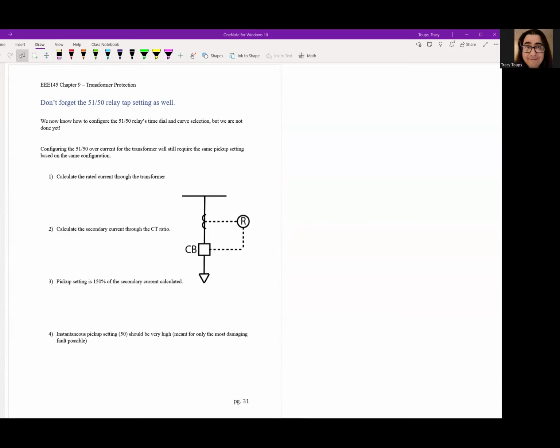But don't forget, we're not done. The other critical part is we always need tap settings. It's a common thing people forget. They don't set the tap setting, and then all that curve coordination won't do anything. Okay, so we did this several times. Let's just go through it real quick. How do we do the tap settings for 50/51? Remember, whatever the rated load current, you have to figure it out through the transformer. It's always I load equals MVA divided by square root of 3 times kV. The big difference is, depending on your high side or low side, you have different load currents, because the low side at the distribution level will be a much higher current than the high side at the transmission level. So you need to do this twice, one for the high side overcurrent and one for the low side overcurrent, if you have it.